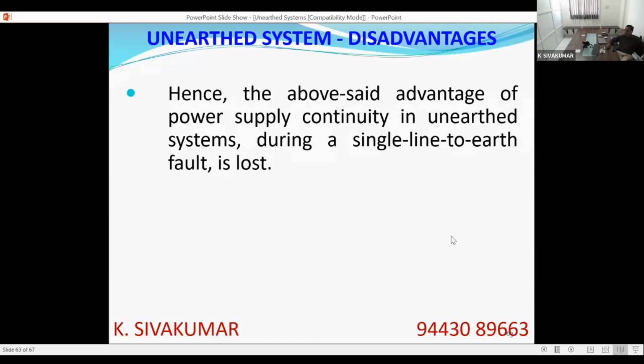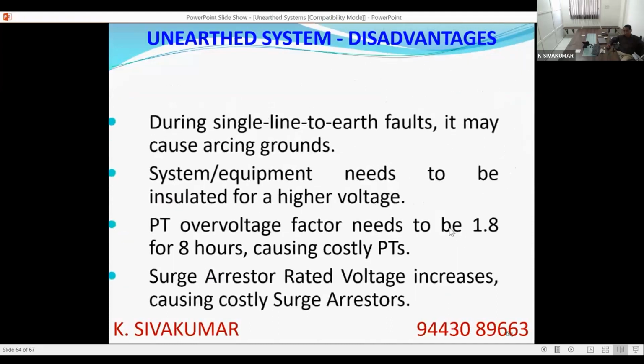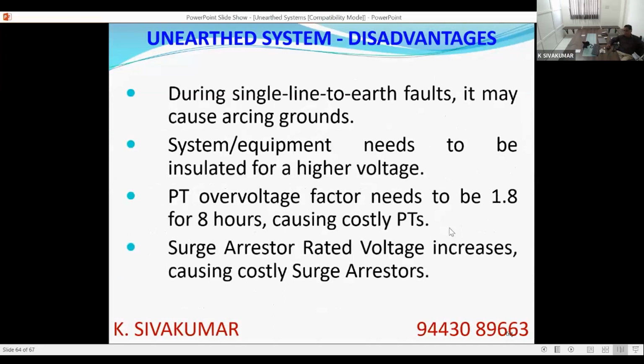So with a line to line fault the current is more, and the breaker will trip or the fuse will blow, causing interruption. So that advantage is definitely lost. And as I said, arcing grounds, because there is a potential jump between earth and the healthy phases, it will keep trying to strike an arc. So these arcing grounds also cause damage to insulators and the terminal equipment. There are records of damage caused to terminal equipment and insulators. So this is another big disadvantage.